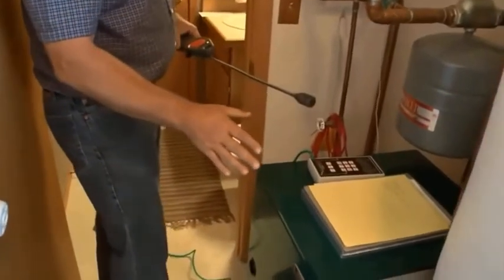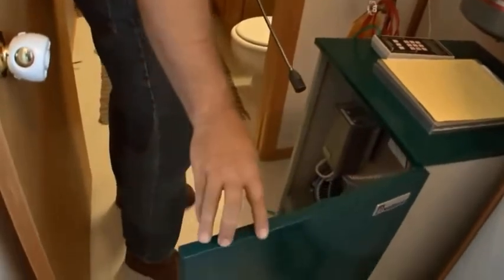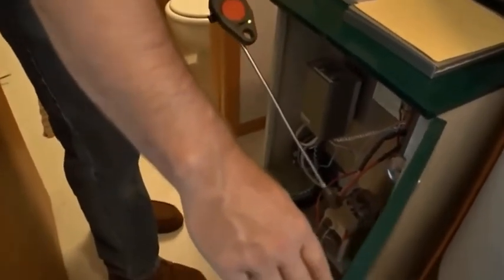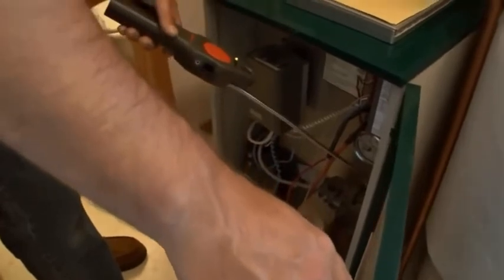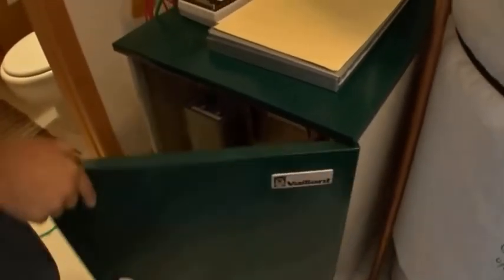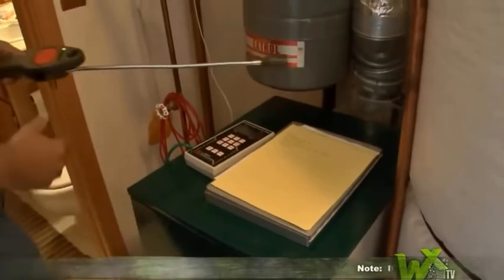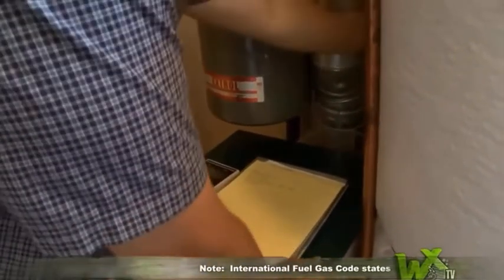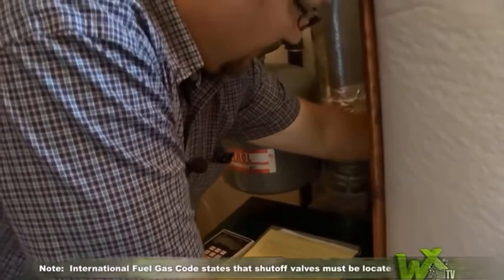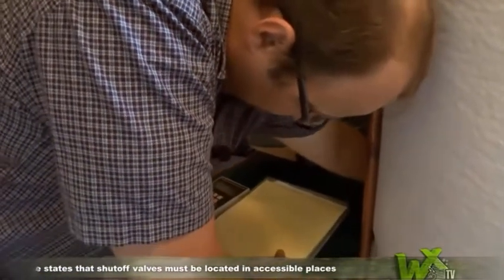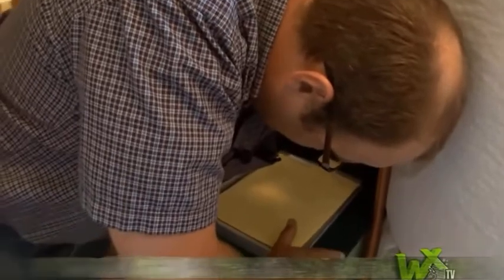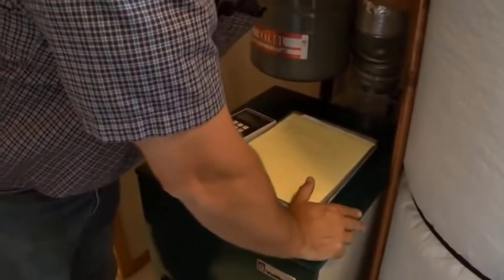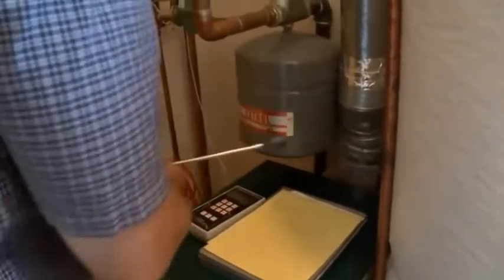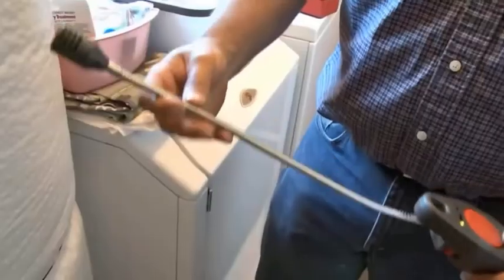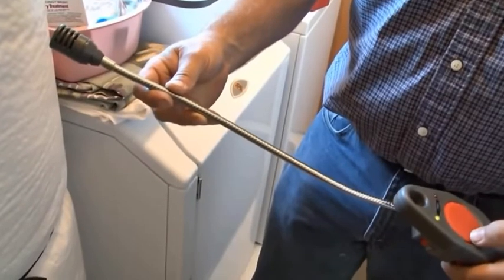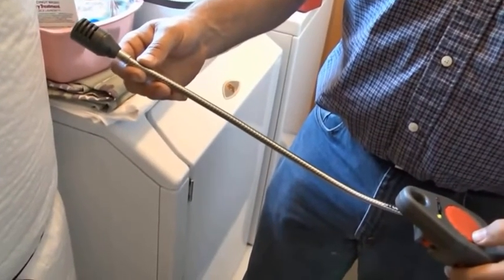One of the issues with this appliance is the gas line actually comes in through the back of this boiler, and it's very difficult to get to the shutoff, and even to get to the gas line. But it's back behind here, and I'm taking the combustible gas detector along that, trying to determine if I have any leaks, and it looks like we're good on this. If there was a leak, this thing would make a sound like this if a gas leak was detected.